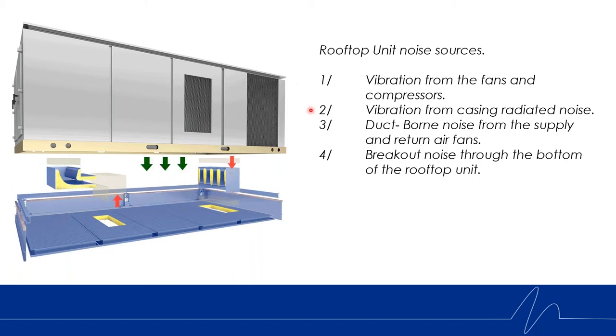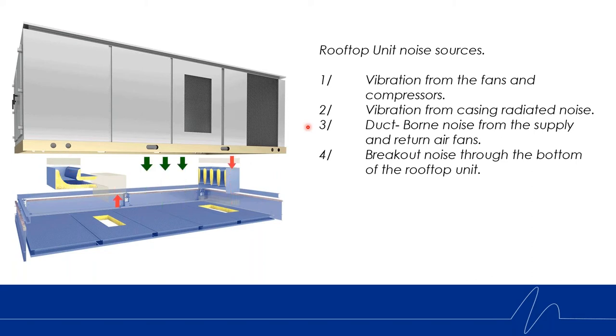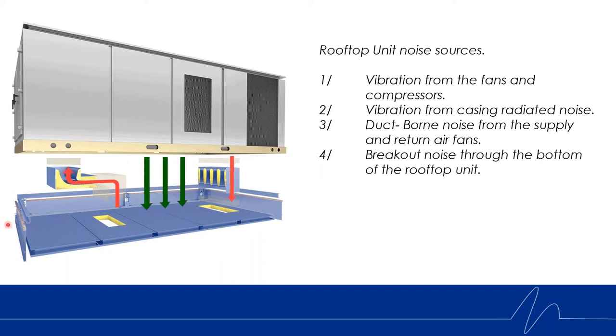The third source of noise is duct-borne noise — that's basically noisy air from the supply and return fans washing through the ductwork and making noise as it comes down into the space. And then we have the fourth and final source of noise: breakout noise through the bottom of the rooftop unit. This rooftop unit is sealed on top of a roof curb, creating a cavity through which noise can travel right down into the space.